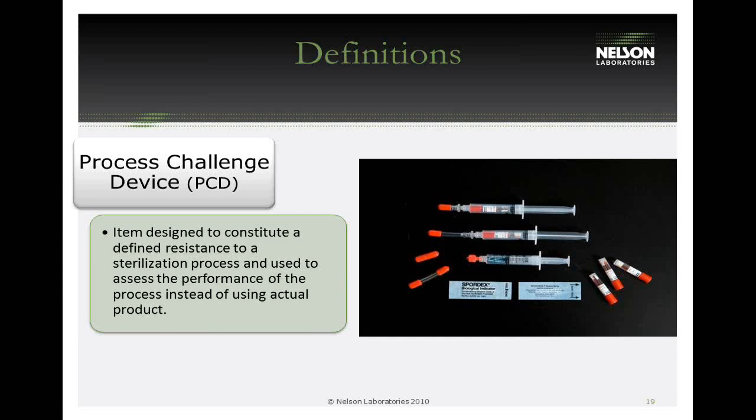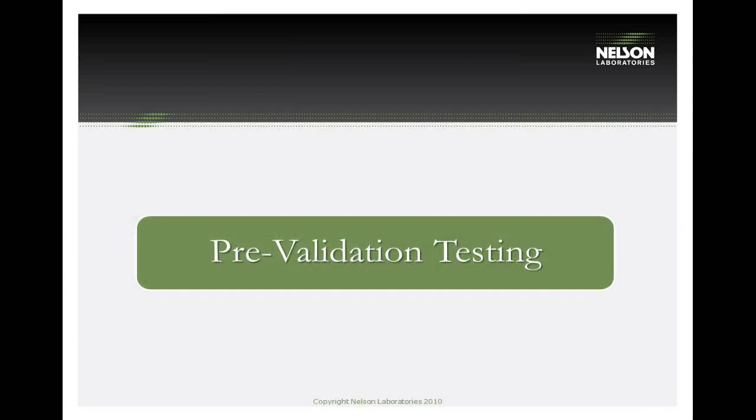A process challenge device (PCD) is used when the actual device is difficult to inoculate, costs over $1,000, or when using actual product would be wasteful. A PCD mimics the sterilization resistance of the product — something simple and inexpensive like a syringe — and the BI is placed inside it instead of in the actual device. The PCD does not need to look like the product; its resistance must be equal to or greater than the most resistant location of the actual product.